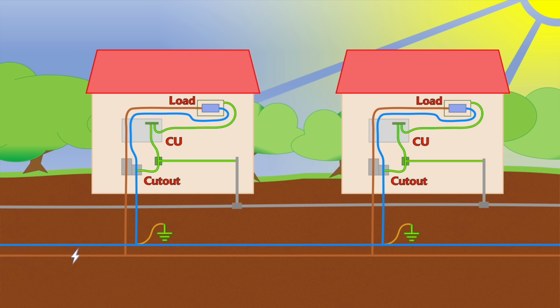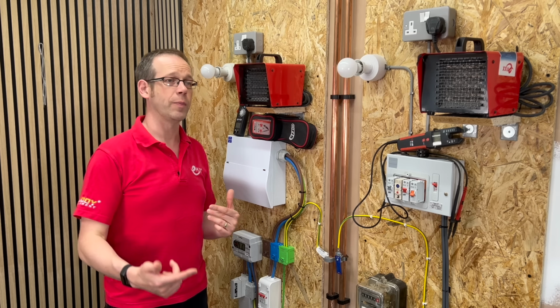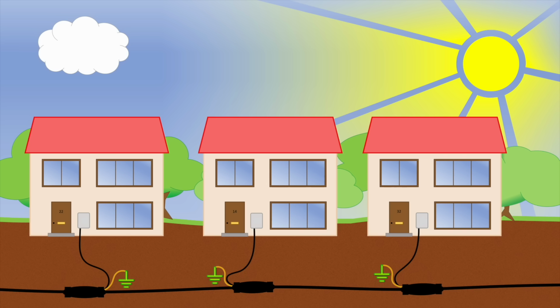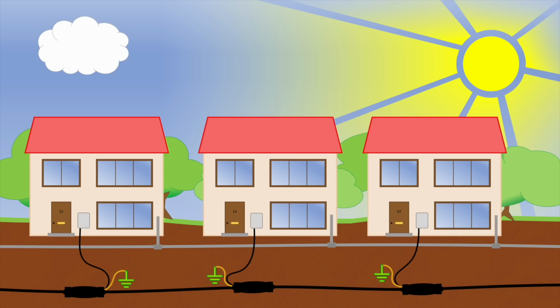The current will split proportionally to the impedance offered by the route back, so the bulk of it will go the way we expect it to, but some of it will go back via the slightly higher impedance route of next door's connection. Of course, this is a very simplified picture. Next door's installation will also be sending current the way it should, which will affect how much of yours goes that way, and indeed the positions may reverse and more current comes back down your earthing arrangement than theirs. Extend it to multiple properties on the same cable and water pipe and you've got a situation where it becomes very difficult to know where the current will be flowing at any given moment.